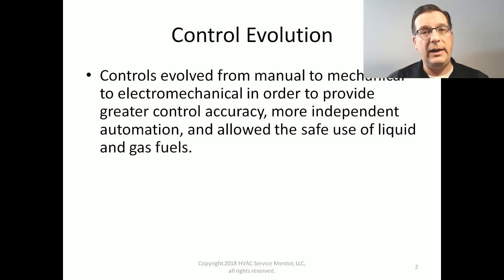An example of electromechanical would be a conventional thermostat with a mercury bulb, right? The mechanical part is the part that moves, the thing rocks back and forth. We have a temperature sensitive element that physically moves in response to changes in temperature, and that movement activates an electrical switch. That's what we mean by electromechanical. And the reason why this evolution happened is multiple reasons. It gives us greater control accuracy, number one. It allows for more independent automation, for two. And for three, it allowed the safe use of liquid and gas fuels.